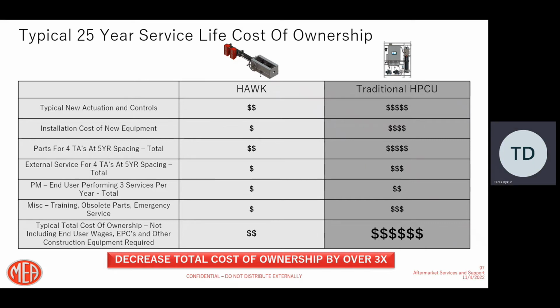Of course, if you have fewer parts and fewer components, the total cost of the actuator for Hawk will be much less compared to a traditional HPCU style system. Additionally, because it's so compact and so simple, it's very simple to install compared to the HPCU style system. As a result, the cost of installation is reduced dramatically. Same applies to any type of maintenance. It doesn't require filters, and doesn't require changing fluid during turnarounds. As a result, there's a major cost reduction over time. We estimate that total cost of ownership decreases by approximately 3 times if you compare Hawk to a traditional HPCU.